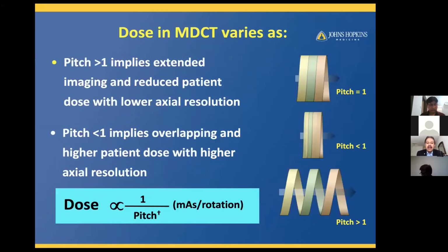Why is the pitch important? Because here is a situation showing the radiation dose in a patient varies with pitch. If the pitch is 1, it means you are acquiring the data without any anatomical gap, by placing one slice after the other. For example, it's like a slinky. If you have slinkies all together, there is no gap, that's equal to a pitch of 1. But if the pitch is greater than 1, you're acquiring the scans, covering the patient quite fast, whereas you leave some gaps in between. That's a pitch greater than 1, which implies extended imaging and reduced patient dose.